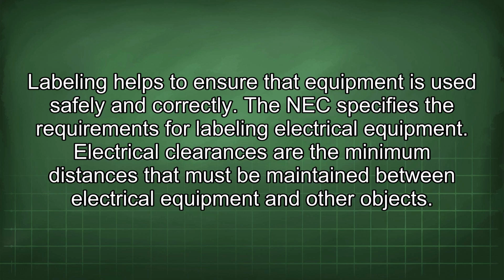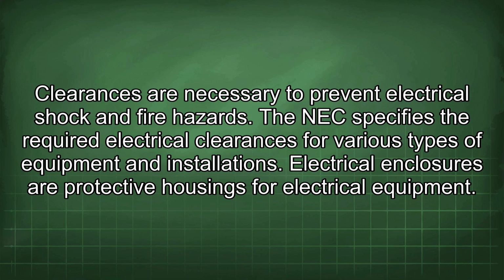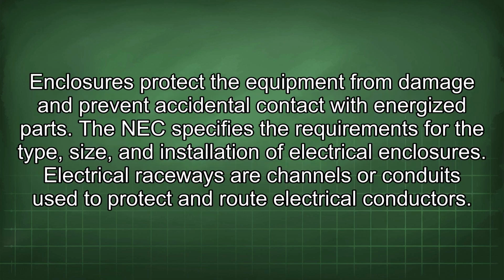Electrical clearances are the minimum distances that must be maintained between electrical equipment and other objects. Clearances are necessary to prevent electrical shock and fire hazards. The NEC specifies the required electrical clearances for various types of equipment and installations. Electrical enclosures are protective housings for electrical equipment. Enclosures protect the equipment from damage and prevent accidental contact with energized parts. The NEC specifies the requirements for the type, size, and installation of electrical enclosures.